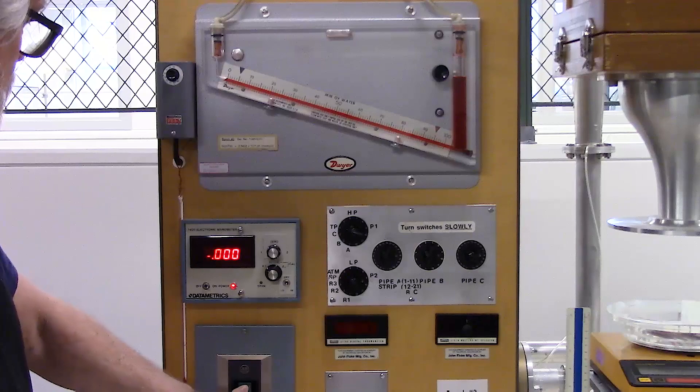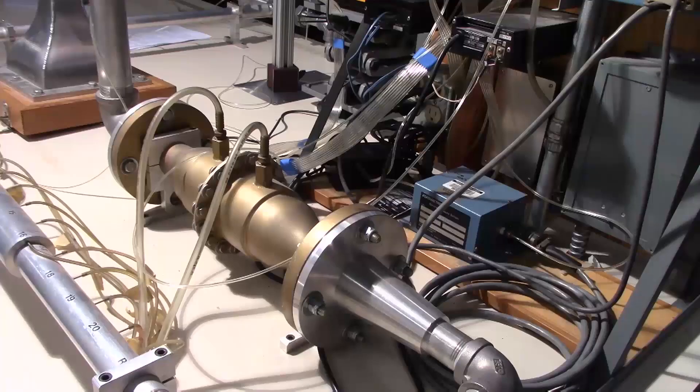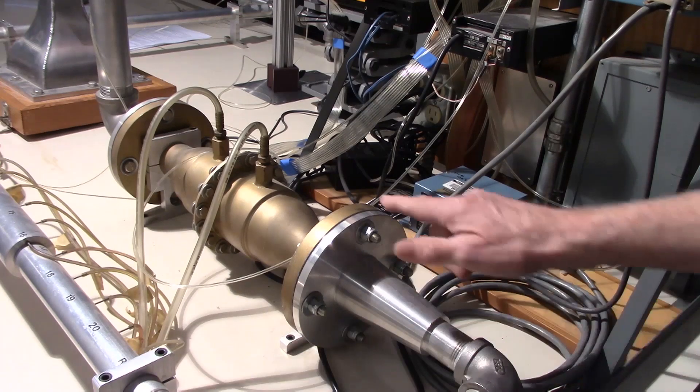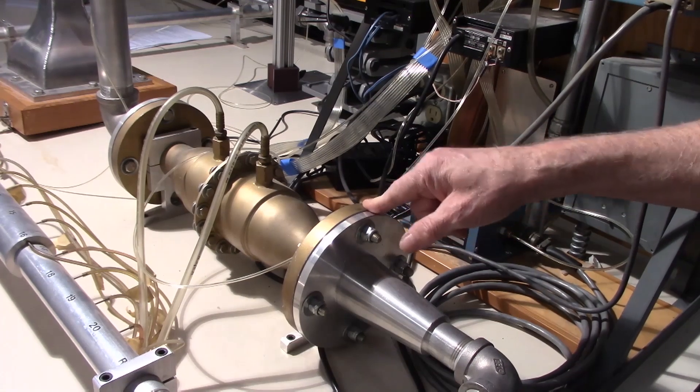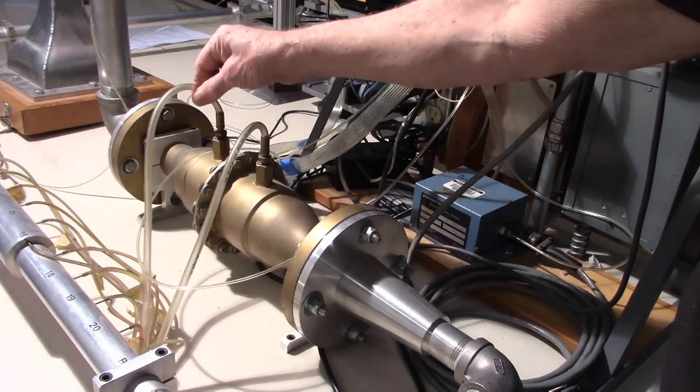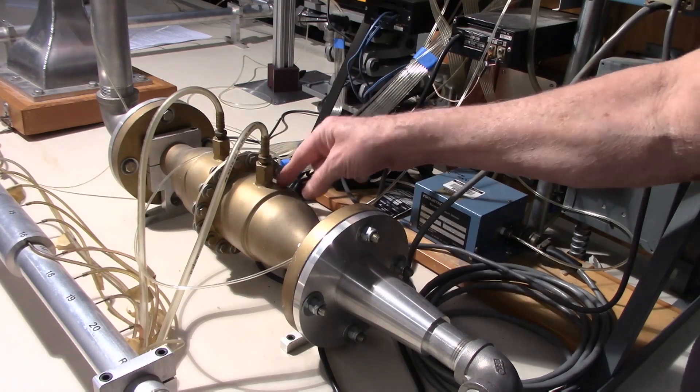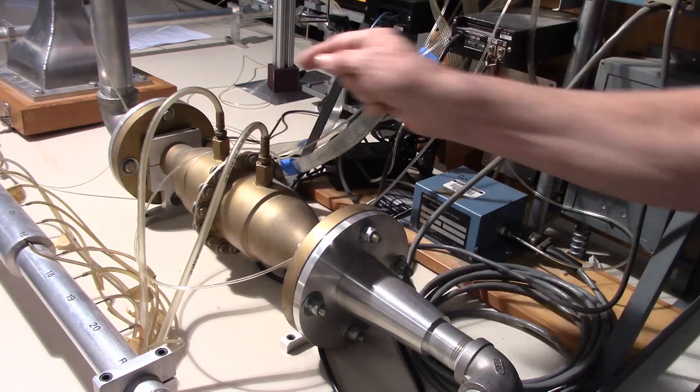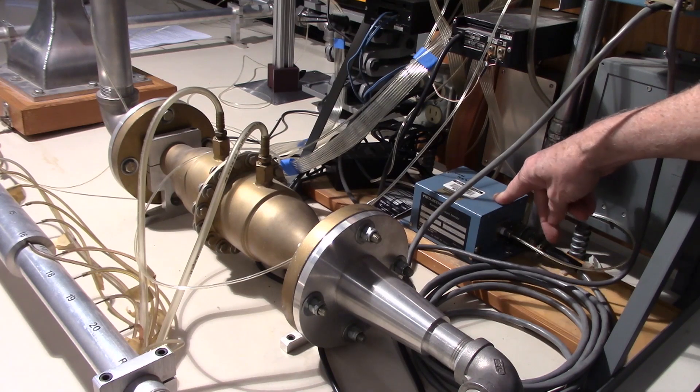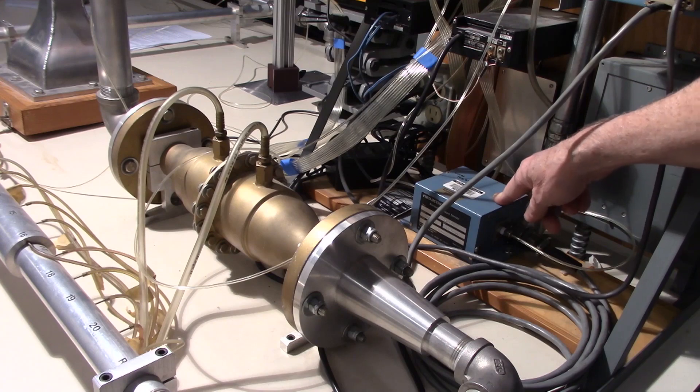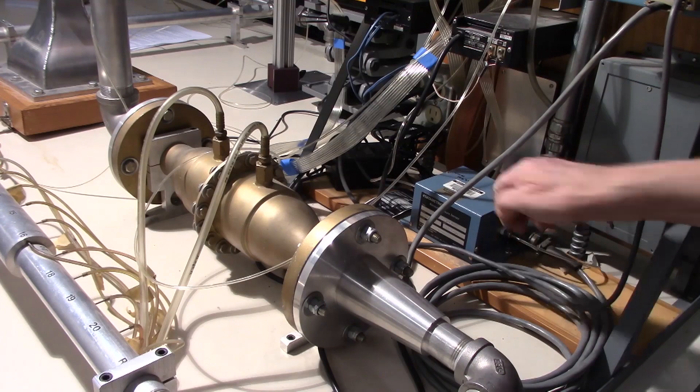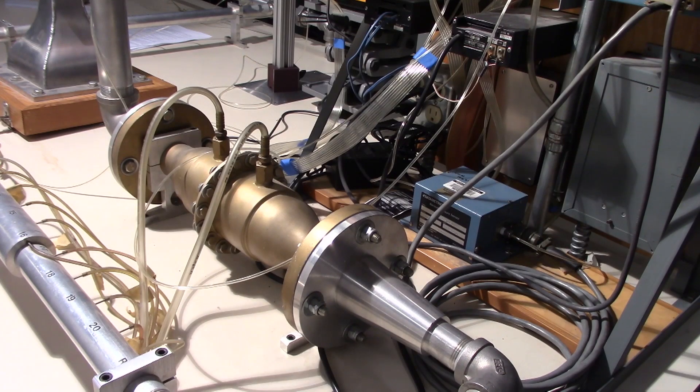We can turn on our compressor using this switch here. Here's a look behind the instrument panel. You can see our flow is routed through this calibrated laminar flow element here. These are the taps that go up to our inclined manometer on either side. This is the high pressure side and the low pressure side. Over here is the differential pressure transducer that we read our pitot tube with. This is the low pressure tap and the high pressure tap. These are both routed to the high pressure and low pressure switches on the front of the control panel.